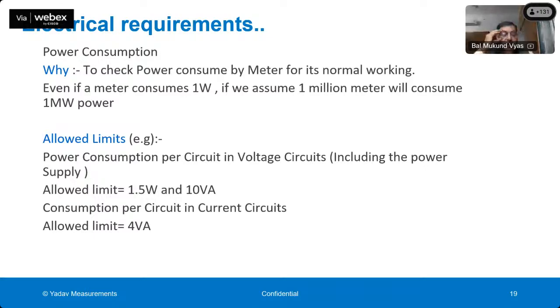Remember, the power consumed by the meter is not measured by the meter, so it has to be paid by the utility. As a consumer, we are not paying for the power which is consumed by the meter itself. There are various limits specified for smart meters, or a meter with a communication circuit, because if a meter has a communication circuit, then more power is required. So the allowed limit for smart meters is more than for normal meters.